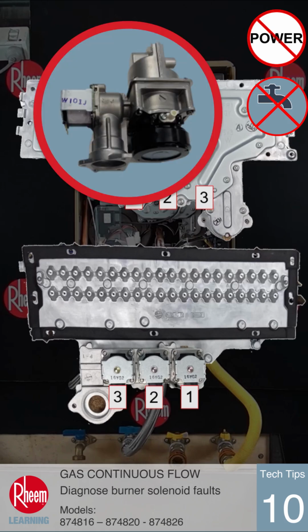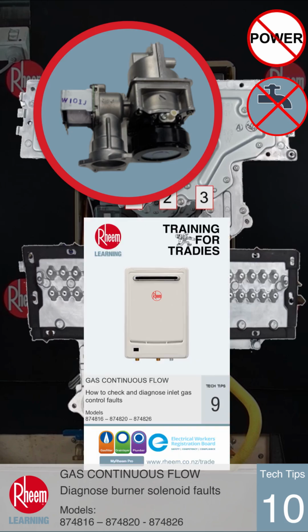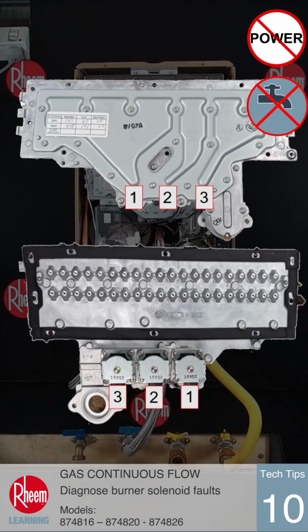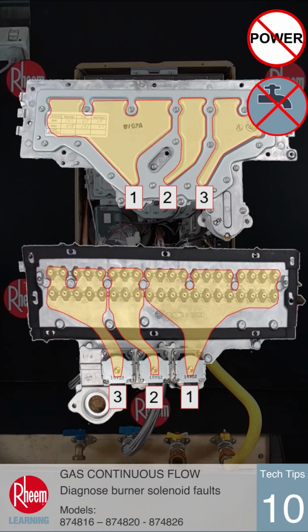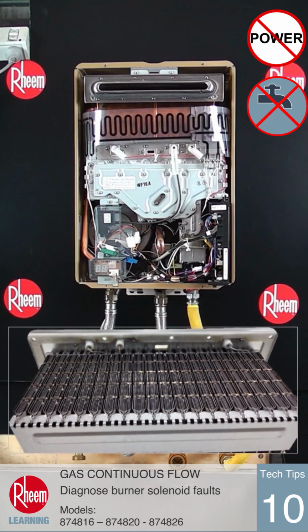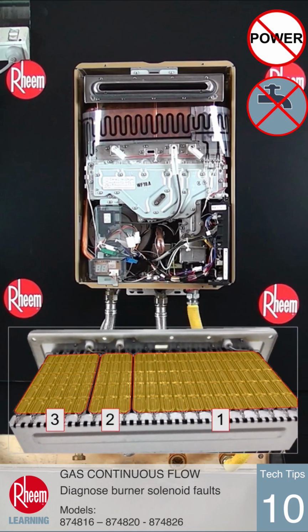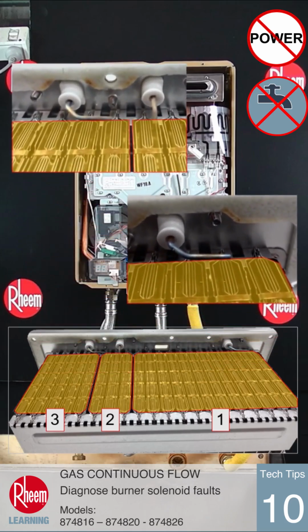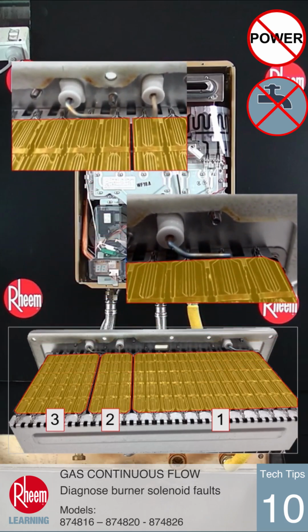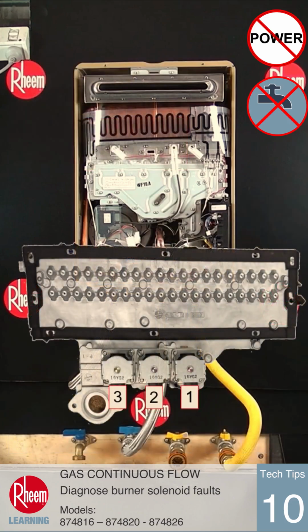The inlet gas valve assembly should always be checked first to rule out any issues there, and this is covered in Tech Tips number 9. Once a flame is detected at the flame rod located on the middle part of the burner, being controlled by solenoid 2, solenoids 1 and 3 are opened to operate the full burner. The second flame rod located at the left side of the burner will detect the flame there. These solenoids can be turned off individually during operation. This will reduce heating during low demand and water flow for normal operation.